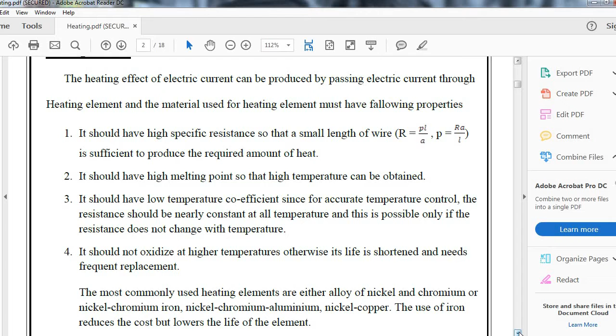It should have a low temperature coefficient, since for accurate temperature control the resistance should remain constant at all temperatures, which is possible only if the resistance does not change with temperature. It should not oxidize at higher temperature, otherwise the life is shortened and it needs frequent replacement. Most commonly used heating elements are alloys of nickel and chromium, or nickel chromium iron, or nickel chromium aluminum, or nickel and copper. The use of iron reduces the cost but lowers the life of the element as it gets oxidized easily.